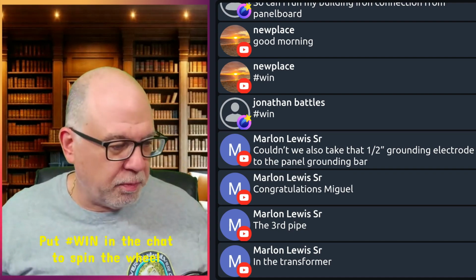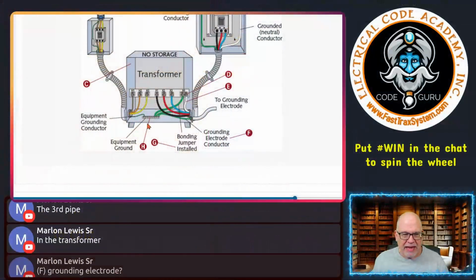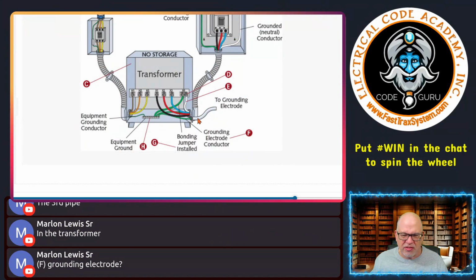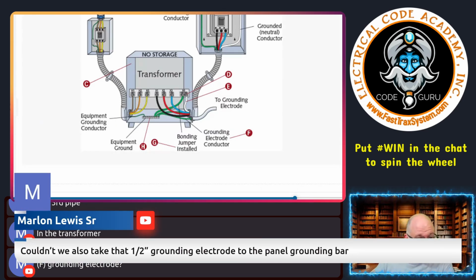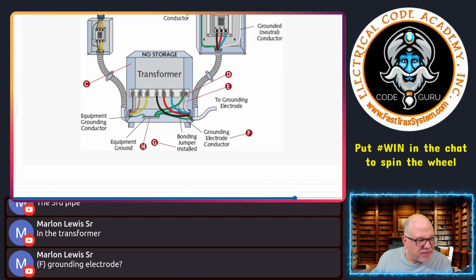So that's why in this picture here, people ask all the time, why didn't you take this right here and connect it right here to the XO? Because this system bonding jumper was sized properly, I'm allowed to take it here to the bus, that type of thing. All right, Marlon, let me see if I can dissect your question here two hours into this. Could we also take the grounding electrode to the panel ground bar? I think I just answered your question.